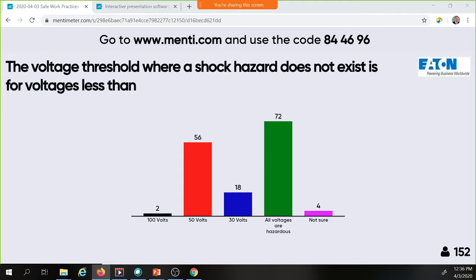If you think about what 70E tells us, now I personally could be in a couple of these camps, right? I could be in the camp that says all voltages are hazardous for a few different reasons. Even if you are below the threshold of what we categorize as a shock hazard, say it's 15 volts or 24 volts, and I'm on a ladder, I could say that the startle factor could knock me off that ladder. It could cause me to fall.